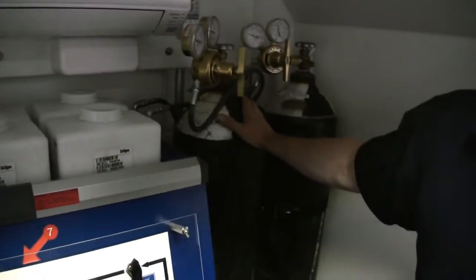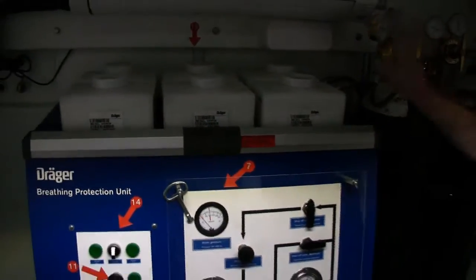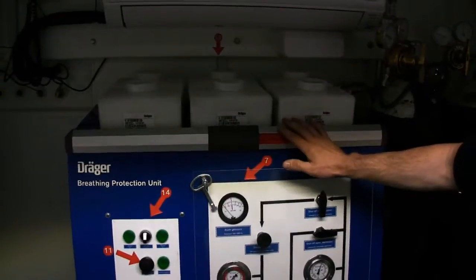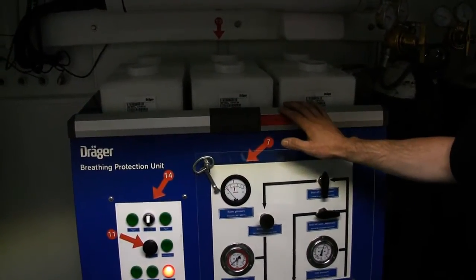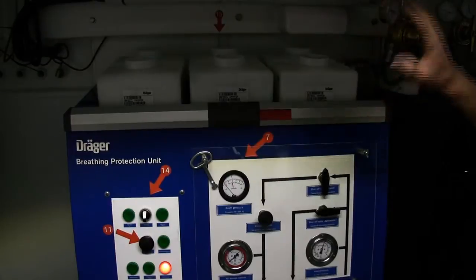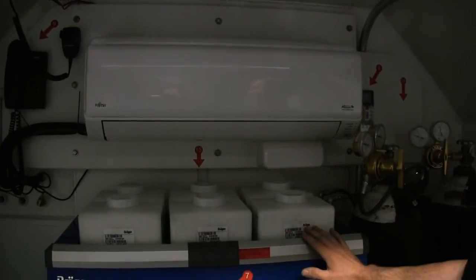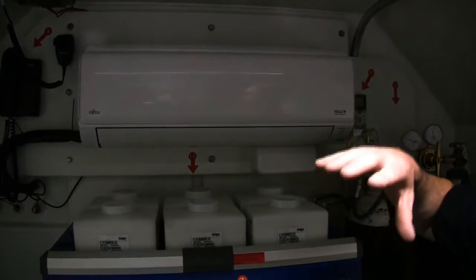So again, it's an either or generated from the tanks. These are just oxygen cylinders on their own. So you just regulate down to the number of people you have. We have breathing air cylinders over here but they're only to maintain positive pressure. So this system controls the cylinders and works to keep 200 Pascals in here. So if you don't have your mine air and you're not purging 100% and relieving, then at 200 Pascals this opens and closes valves to maintain 200 Pascals. If you're cooling, you're going to condense the air in here and you're going to drop pressure. So these will compensate for that. If you're heating, it's going to build pressure and it's going to relieve and this is not going to operate.